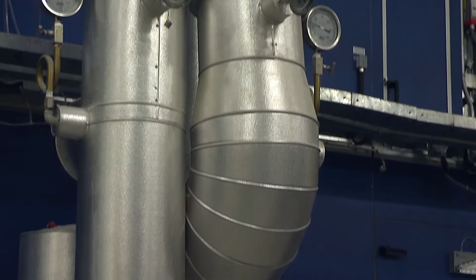Building Management System, BMS. Temperature sensors, humidity sensors and carbon dioxide sensors provide feedback to the Central Building Management System, BMS, which in turn causes variable volume boxes, chilled water valves, and outside air dampers to maintain space occupant comfort within the selected areas. The sophisticated BMS system recognizes the building population density and adjusts the amount of outside air that is introduced for ventilation purposes, thereby saving considerable cooling energy.